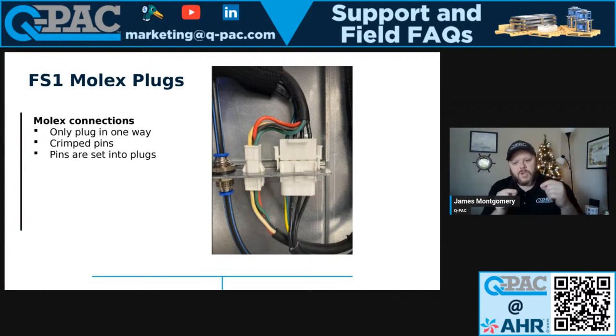So you want to make sure that those come together correctly. Make sure there's no massive gap, because what that gap's going to do, when those two pins come together, is create heat. And it's going to create resistance. And that resistance, the byproduct will be heat, and it'll eventually deteriorate and destroy that connection, which will lead to a premature fuse failure or a failure of that cable and connection.